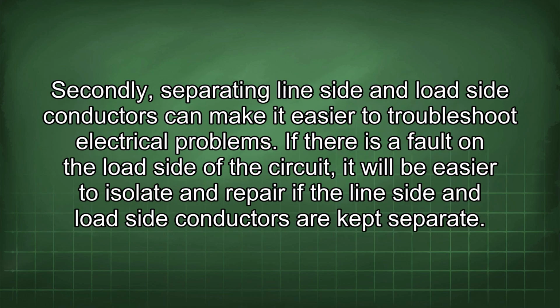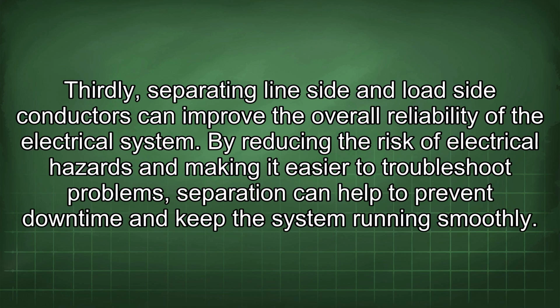Secondly, separating line-side and load-side conductors can make it easier to troubleshoot electrical problems. If there is a fault on the load side of the circuit, it will be easier to isolate and repair if the line-side and load-side conductors are kept separate. Thirdly, separating line-side and load-side conductors can improve the overall reliability of the electrical system. By reducing the risk of electrical hazards and making it easier to troubleshoot problems, separation can help to prevent downtime and keep the system running smoothly.